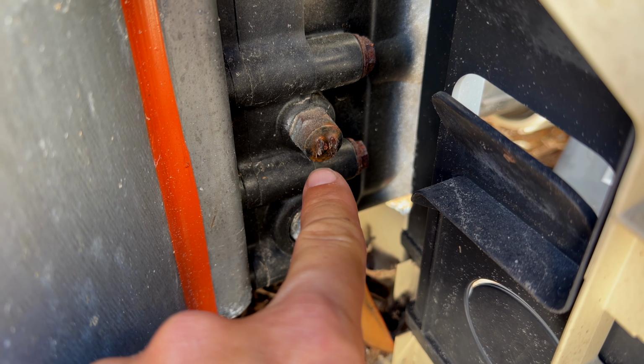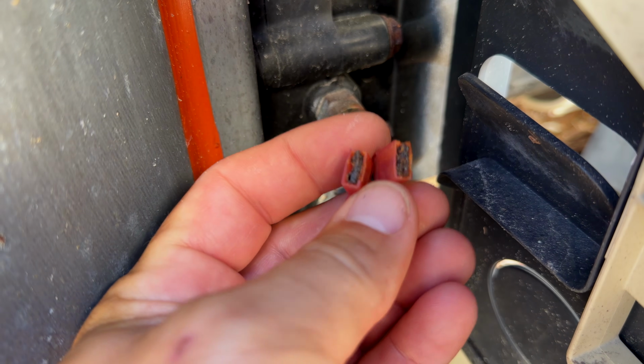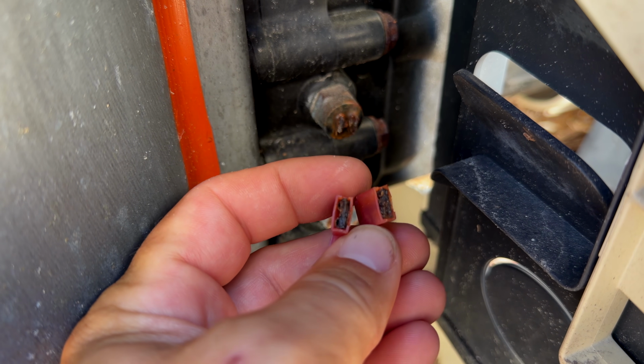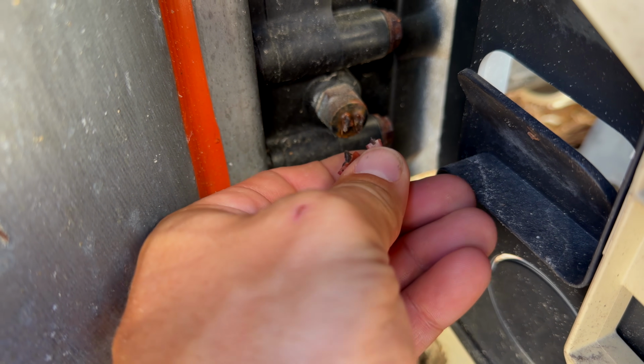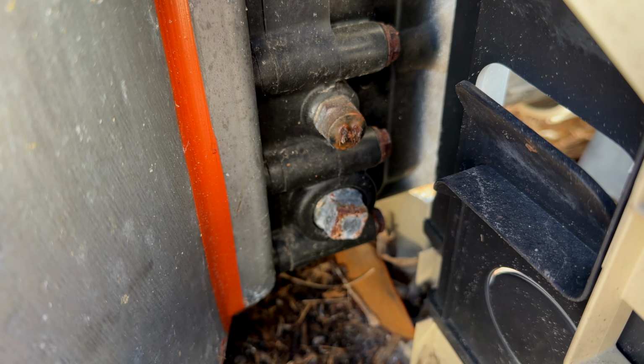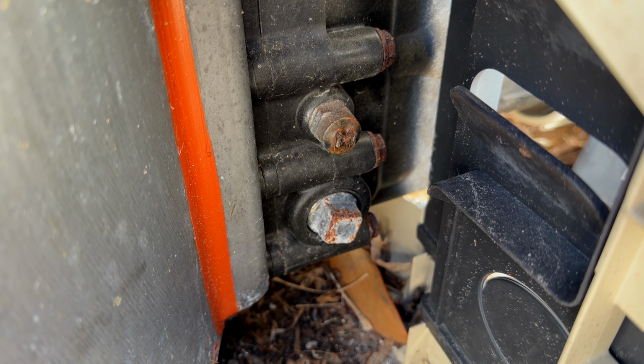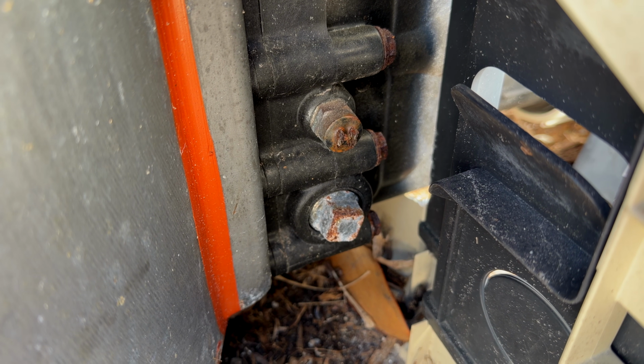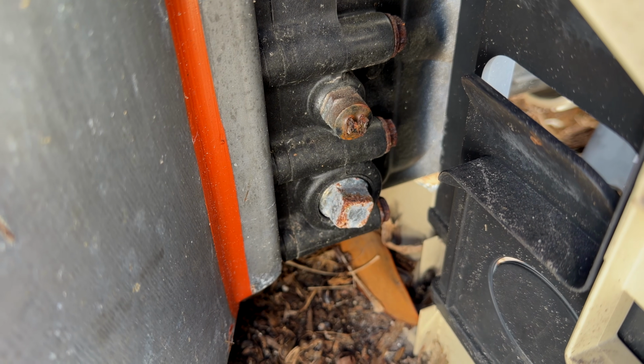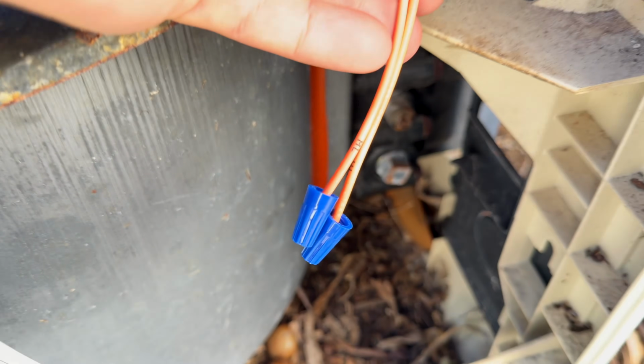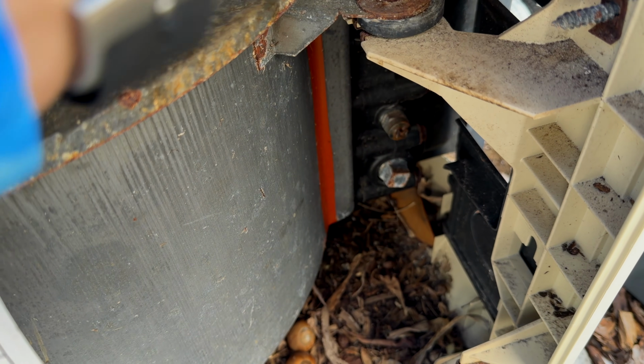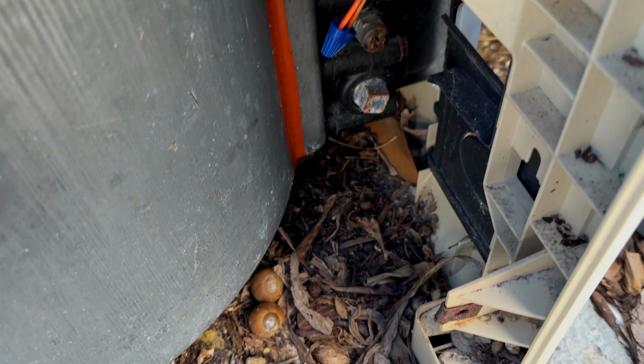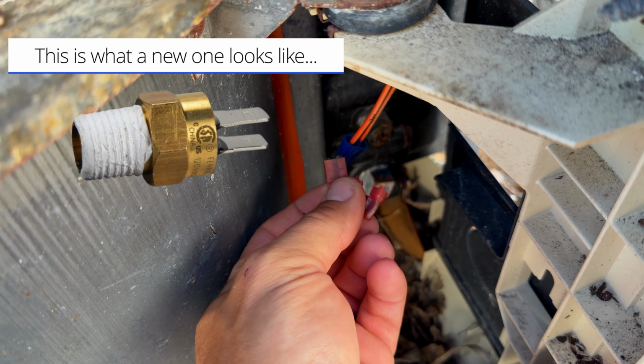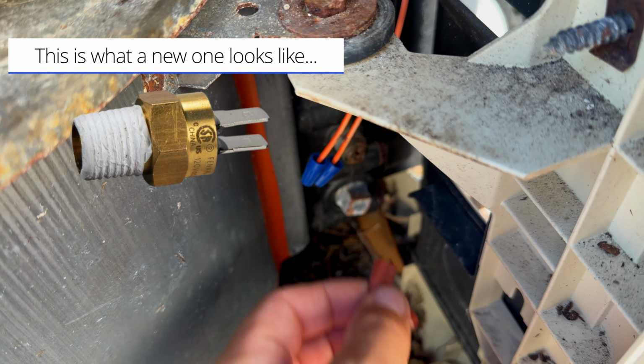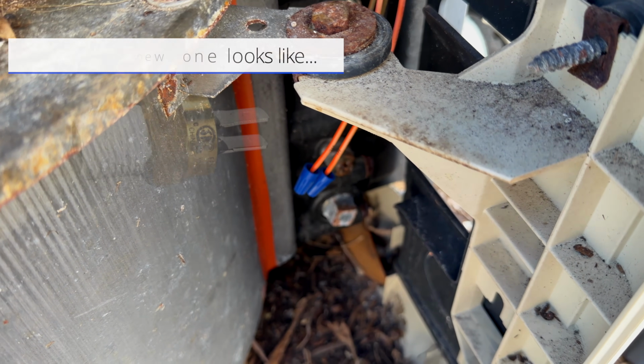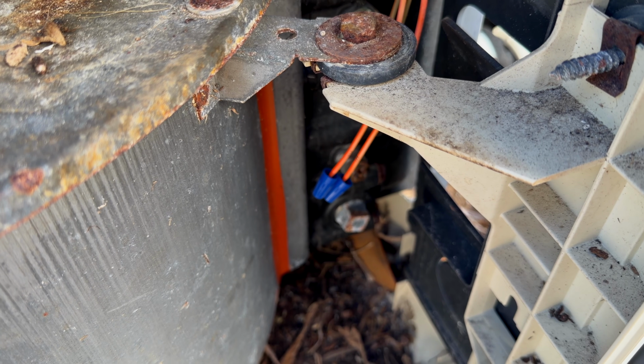And so I already cut these wires and everything, but the problem is there's so much rust and corrosion in these flag terminals that it wasn't making a solid connection. And so it's basically saying that there's no high limit switch closing, and it gave that error. So it actually goes to these two orange wires here, and they go down here, and just imagine these flag terminals connected to that, and they plug into it, and that's what makes that connection to verify that there is a high limit switch active and working.